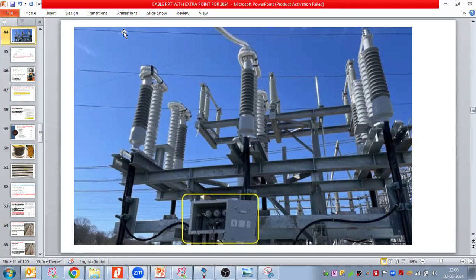What will be the problem, sir, if we run with both ends SVL? Only the induced voltage will be there, right? That is the only thing. If one end is solidly bonded and the other end we install the SVL, the open circuit voltage will be there, right? Yes, voltage would be there. If both end SVLs are installed, is there any place where that was used? Like both end SVL installing. So what could be the issue? The issue would be the induced voltage.